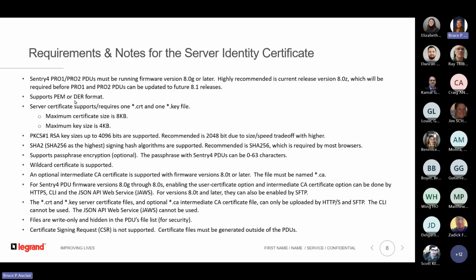The PDUs support certificates in PEM or DER formats. They require a CRT file, any name ending in .crt, and a key file ending in .key. The maximum certificate size is 8 kilobytes, and the maximum key size is 4 kilobytes. PKCS #1 RSA key sizes up to 4,096 bits are supported, though we recommend 2048-bit due to the speed trade-off — a higher RSA key size slows communication with the PDU and makes web pages load slower. The signing algorithm supported is any SHA-2, with SHA-256 being the highest and recommended, since it's required by most modern browsers to meet minimum security requirements.